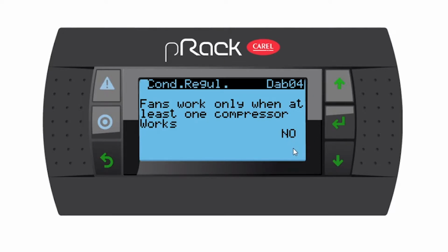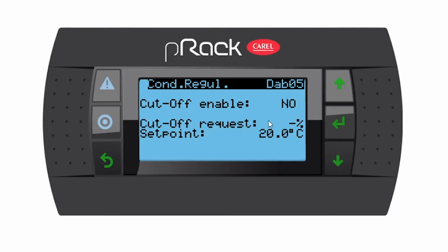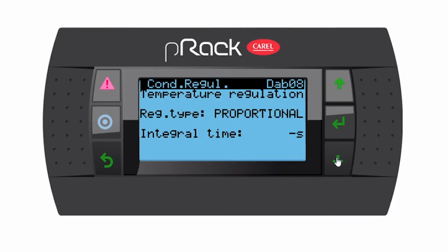So what this means is the fans will always try to regulate the 38 degrees condensing, regardless if a compressor runs or not. If you say yes, a compressor has to run for the fans to run. I'm going to leave this on no and go down. Cutoff enable, no, but you have the option to set a cutoff and some set points. Let's go down. Temperature regulation type, proportional, yes.